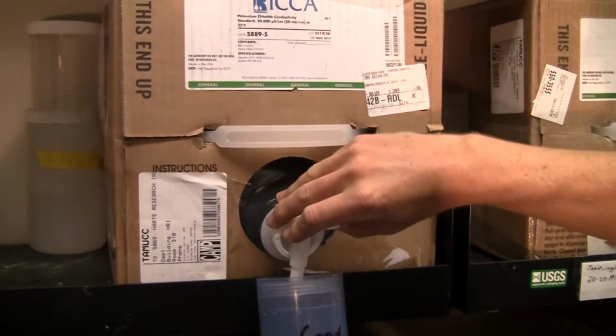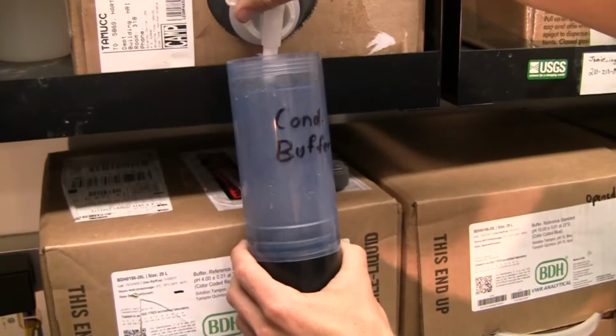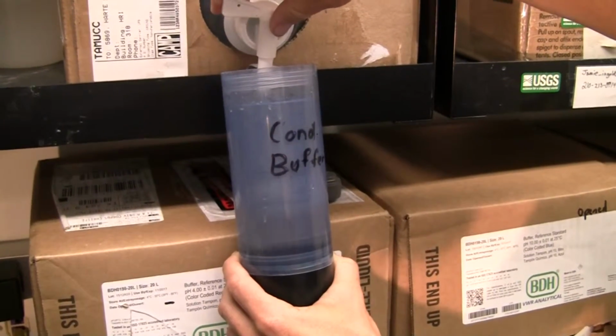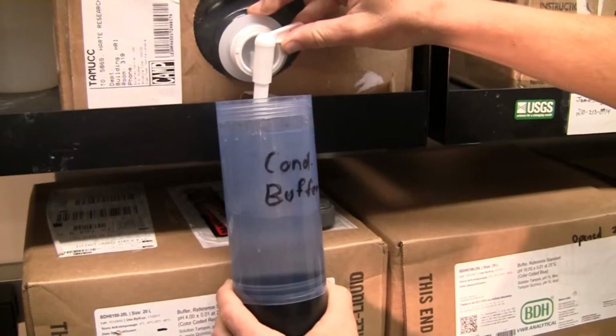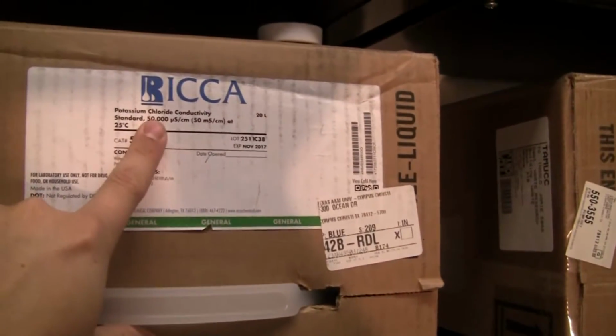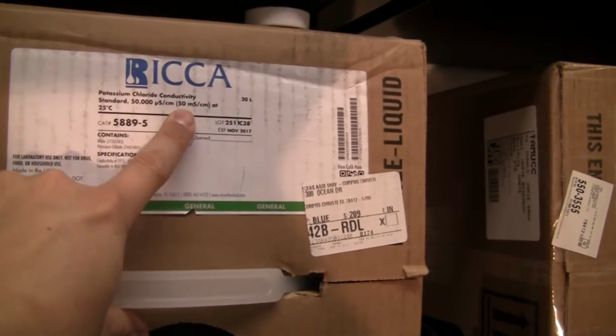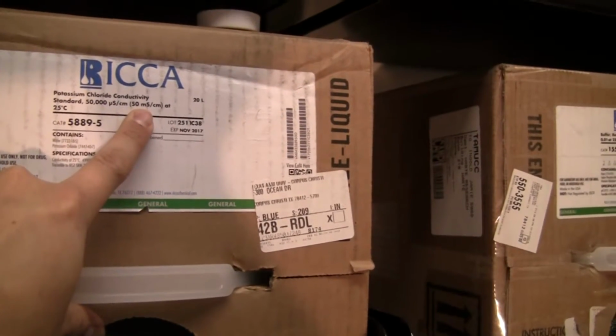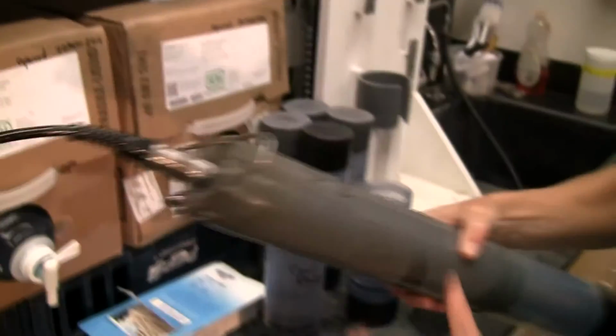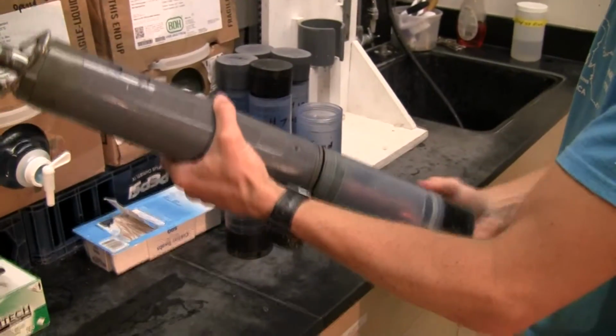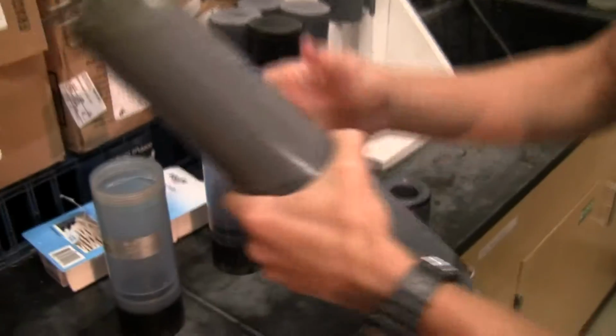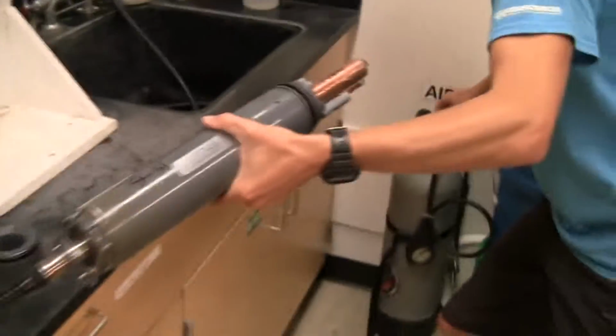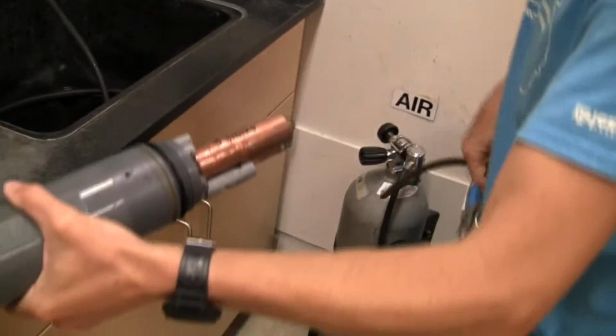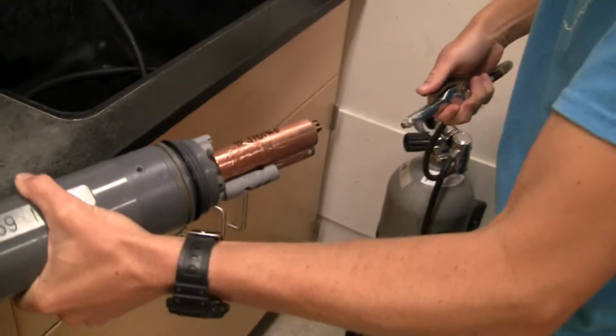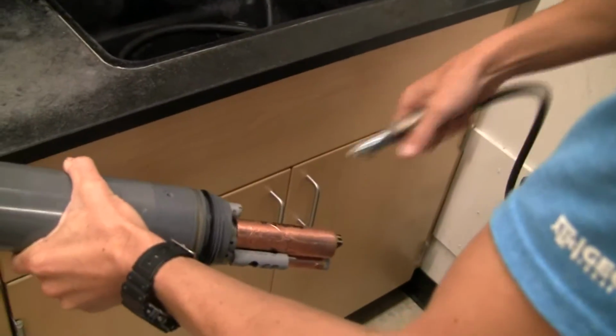Okay, so now what we're going to do is we're going to fill the buffer up. So now we pour the liquid of the conductivity buffer inside the jar. Make sure that there is enough in order to completely cover the sensor. And we also take note to make sure that we have our units correct. So this standard is 50, and that's what we're going to be writing down on the sheet. So now we take our unit and remove the cap. We take our pressurized air to blow off whatever water or liquid that's on the sensors to clean them with.